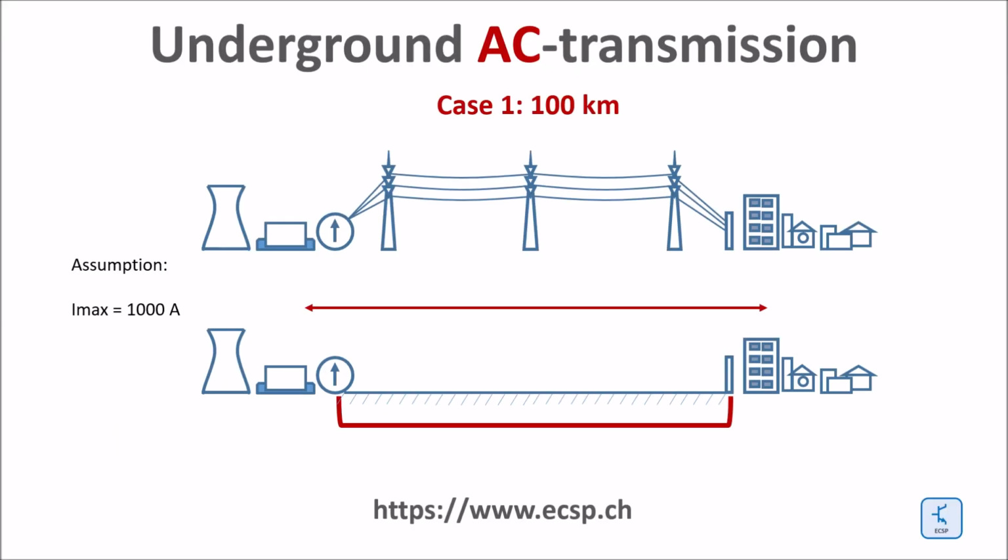Let's now further increase the cable length to 180 kilometers. With 180 kilometer cable length, I need to have heavy compensation at both cable ends. For the traditional transmission line, however, I'm still within the limits tolerated without compensation. What you can also see is that the charging current of the power line is still pretty small. This is the green curve here, whereas the charging current of the cable, even compensated, is already reaching the maximum limit tolerated. So there is very, very little room for additional load current in the cable.